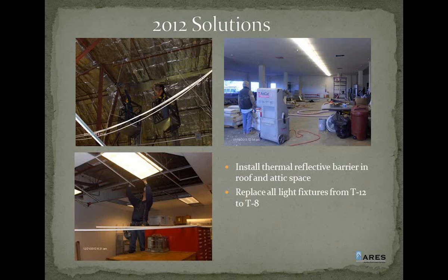We got a thermal reflective barrier. We took the entire space apart section by section because the building had to remain occupied. We took the ceiling down, we put the barrier up to keep the heat from coming in, but also to keep the cool air from going out. We changed the temperature in that plenum. In the summertime, it averaged about 115 degrees. We reduced it to 80 degrees.